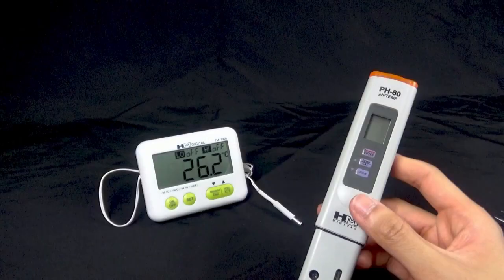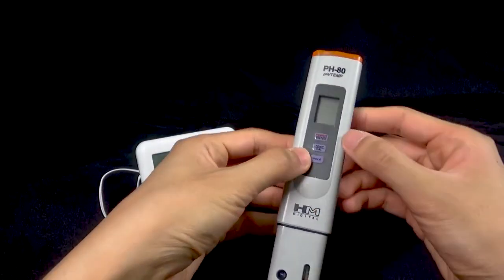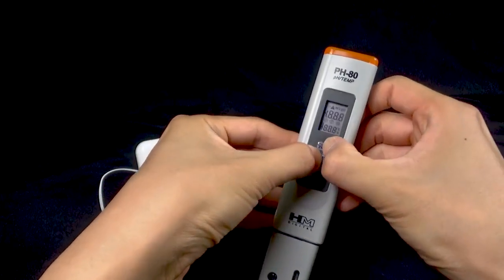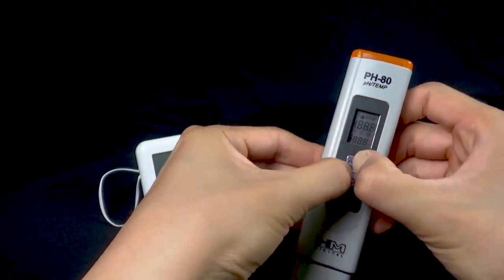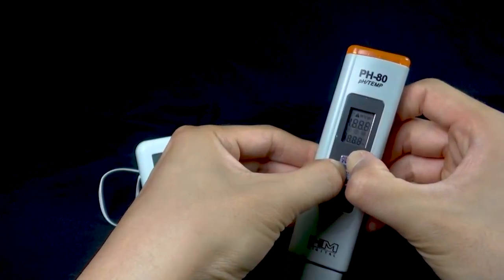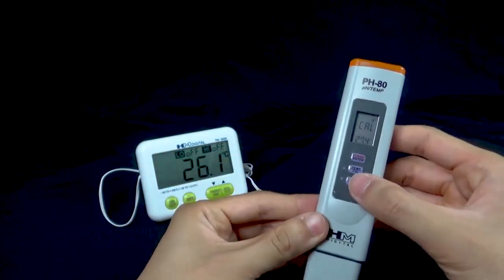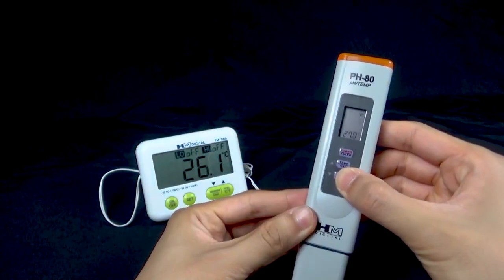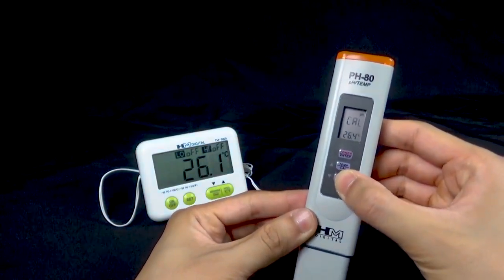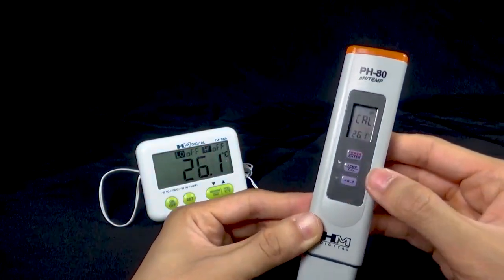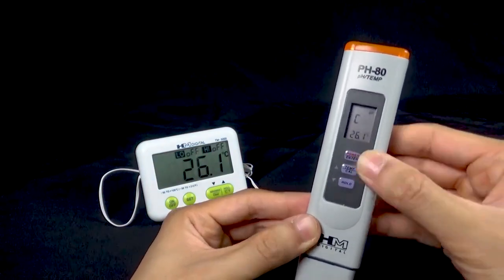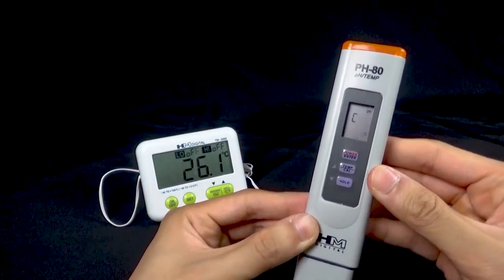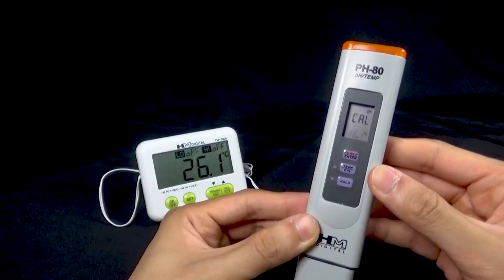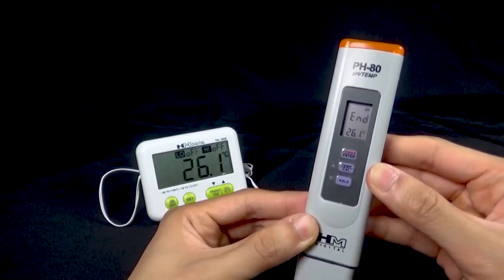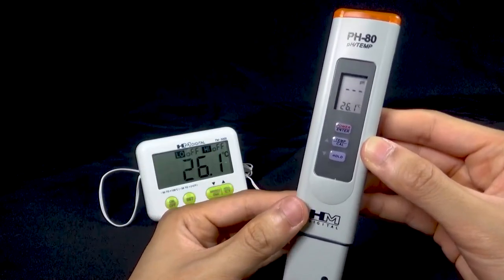If you need to calibrate the PH80's thermometer, only calibrate it to a different, correct thermometer. With the meter on and in the air, press and hold the power and temp buttons at the same time for 5 seconds. Cal and the temperature will flash on the screen. Using the up or down buttons, adjust to the correct temperature. Once you have corrected the temperature, click Enter. Cal will flash on the screen, and then End will briefly appear. The temperature calibration is now complete.